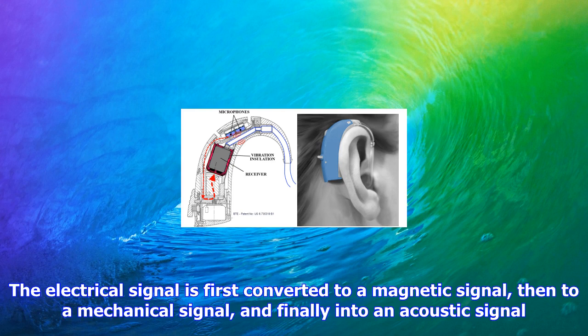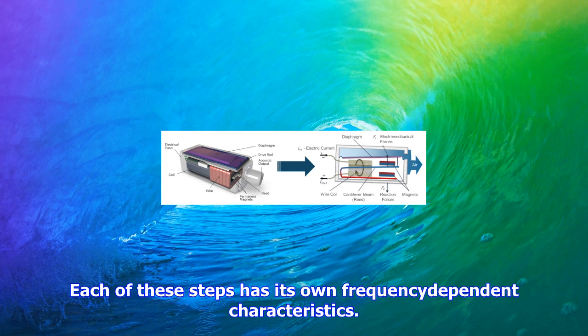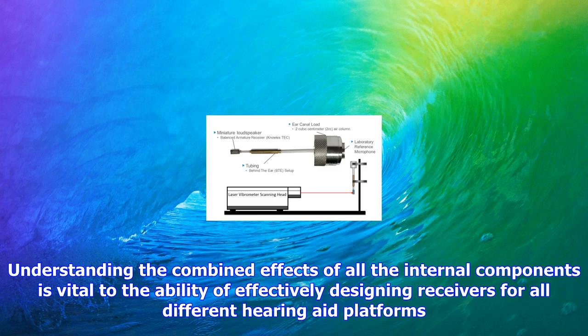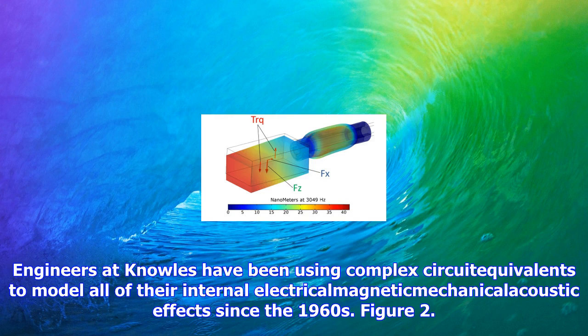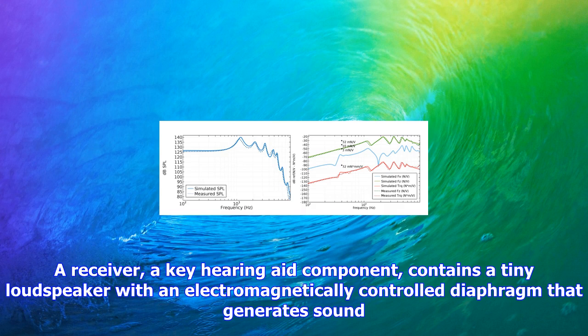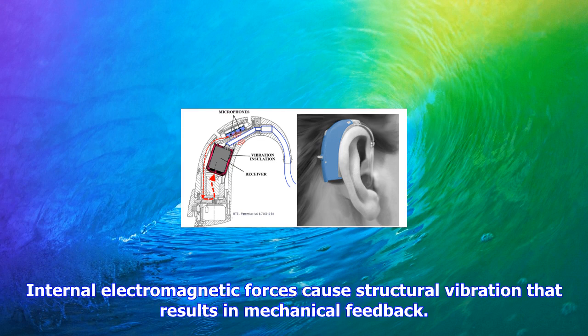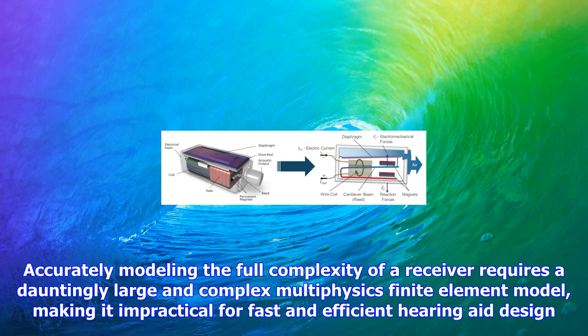The black box model. The receiver's only function is to convert the amplified voltage signal from the microphone into sound. While the construction appears simple, the process is rather complex. Figure 2. The electrical signal is first converted to a magnetic signal, then to a mechanical signal, and finally into an acoustic signal. Each of these steps has its own frequency-dependent characteristics. Understanding the combined effects of all the internal components is vital to the ability of effectively designing receivers for all different hearing aid platforms. Engineers at Knowles have been using complex circuit equivalents to model all of their internal electrical, magnetic, mechanical, and acoustic effects since the 1960s. Figure 2. A receiver, a key hearing aid component, contains a tiny loudspeaker with an electromagnetically controlled diaphragm that generates sound.